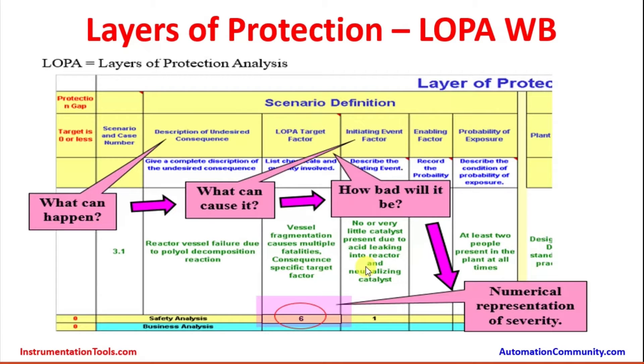The LOPA workbook also captures the initiating factor — which event can cause a particular consequence — along with the enabling factor and probability of exposure, indicating how many people will be exposed in that process area. On the right side, there are different protection layers and the credits associated with each: BPCS Basic Process Control System, operation alarms and operator response to alarms, the safety instrumented system layer, and mechanical protection layers like pressure relief valves and rupture discs.